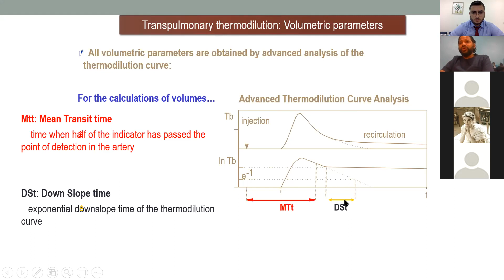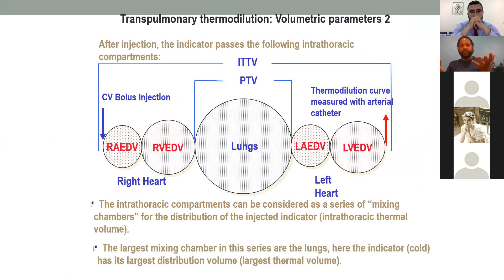So mean transit time is defined as half of the indicator passing the point of detection in the artery, whereas the downslope time is the exponential downslope time of the thermodilution curve. So this is your mean transit time as I showed you here, and that's your downslope time. Now, why is it very crucial? This is very crucial because that's where you get your measurements. This will give you transpulmonary thermodilution volumetric measurements. So it will give you how much volume you're playing with in the heart.